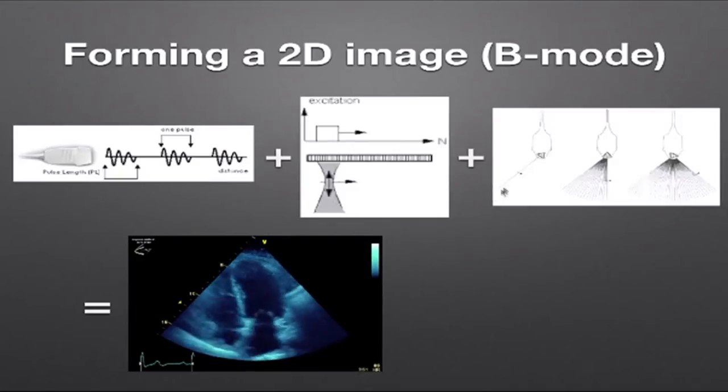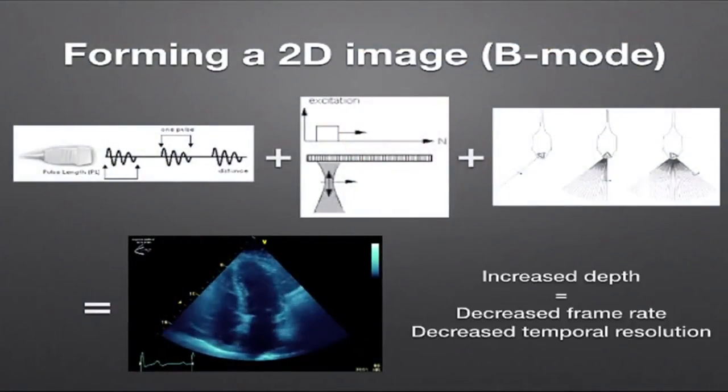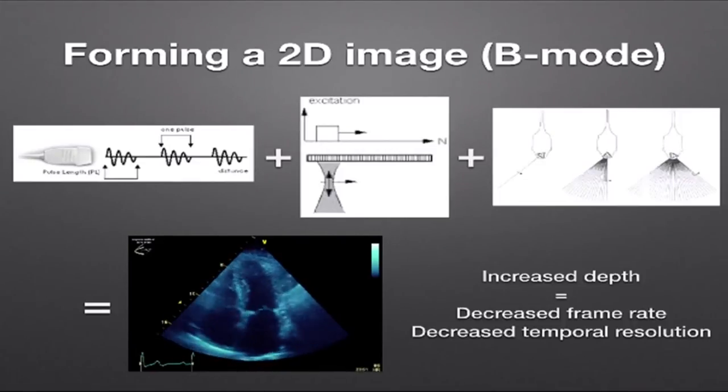The amount of time we must listen for an ultrasound pulse to return depends on the imaging depth — which is why depth is important in image optimisation. Greater depth means the machine must listen longer, leaving less time to generate frames per second. So increased depth decreases your frame rate, which we also describe as decreased temporal resolution, impairing our ability to measure structures accurately within a given cycle.